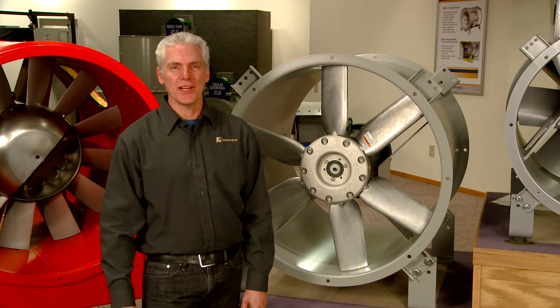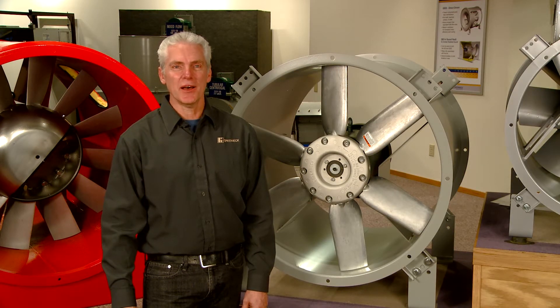Hello, I'm David from Greenheck. I will be showing you how to change the blade pitch of an AX fan. By adjusting the pitch of the blade, you can increase or decrease airflow or pressure for optimal performance from your fan. You can also make these adjustments if your fan motor is overamping.